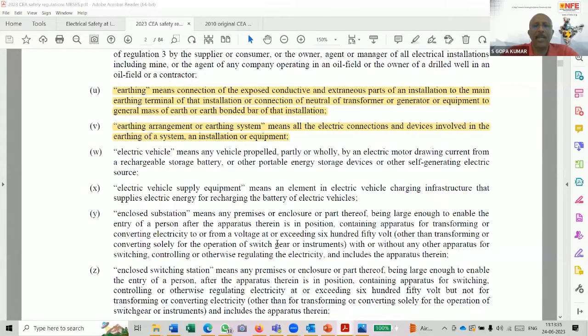Actually, sir, this has some technical background as well. For example, when these two connections were introduced, maybe in the 1950s, ingress protection did not exist, and for most equipment, for example a motor, the earth connections were on the outer casing of the equipment. But later, once ingress protection was introduced in the standards, people started keeping the earth terminals inside a mechanically protected place, either inside the panel board or something like that. But this practice is not popular in India. We still have panel boards where the earth terminals, or the earth bus bar, are extended outside. If the connections are from outside, of course, mechanically they can get corroded or somebody may disconnect them, and those chances are there. So two connections are required.